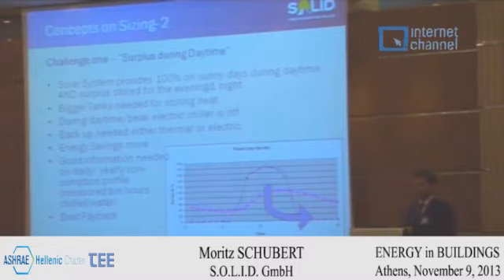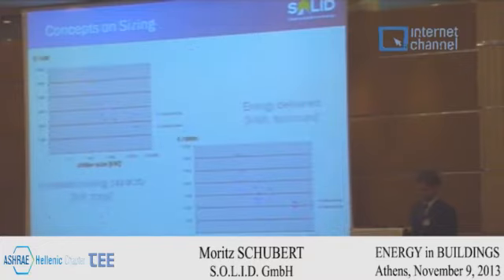By the way, we don't use a cold water storage, because a cold water storage has a rather low delta T. Maybe with a cold water storage you can cool down from, let's say, 12 to 7 degrees, a delta T of 5 Kelvin. But when we use a hot water storage, we have a bigger spread. We can go maybe from 80 to 95, so it's 15 Kelvin. It's double or triple the temperature spread, and so we have only half or a third of the space demand for the energy storage.